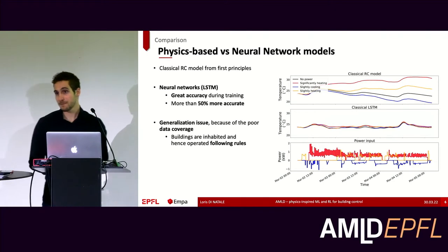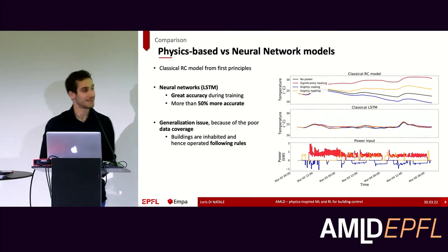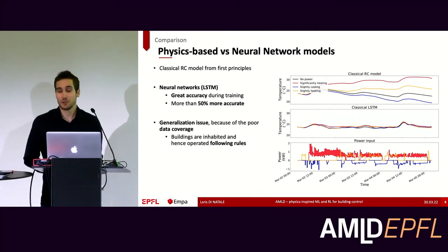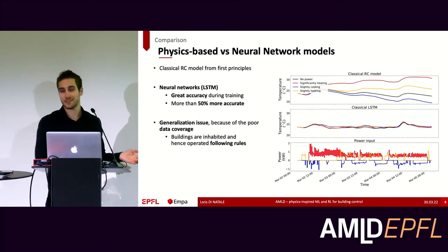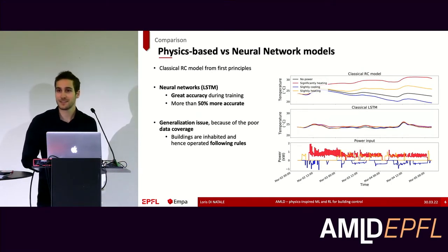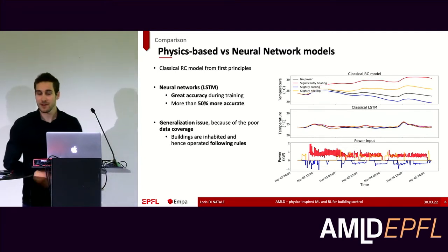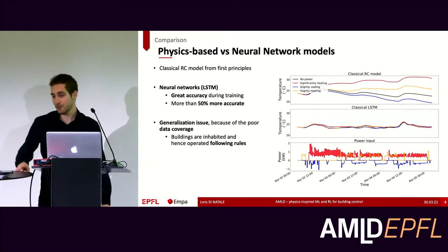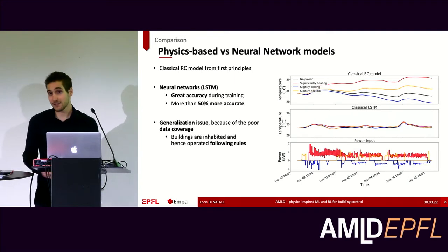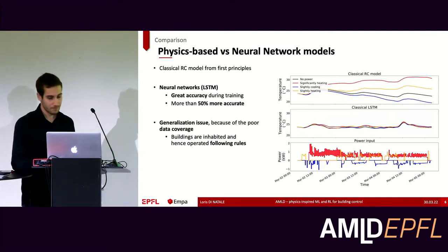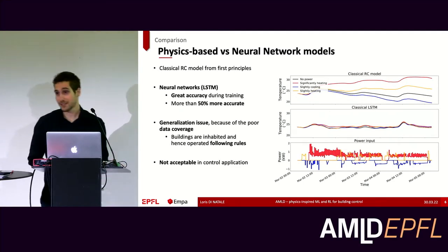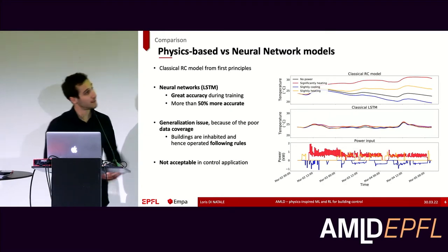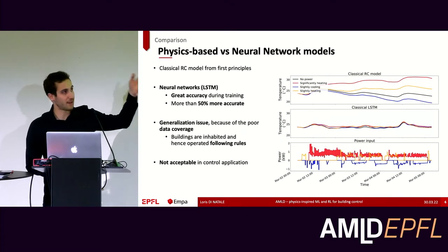You have to be very careful about generalization. In my case, since I'm focusing on buildings, it's kind of always an issue because the data is inherently incomplete. You're forced to cool in summer and heat in winter — you can't have 30-degree temperatures inside, or you won't cool in December. All those situations won't appear in historical data. So when you try to fit a model, it won't know how to react to that kind of new input. For control applications, that's not acceptable. You can't even distinguish between heating and cooling — how do you want to control that building?